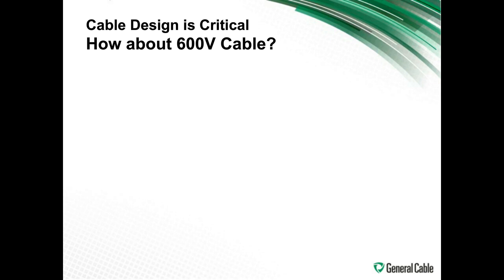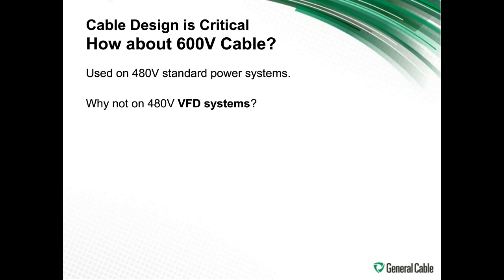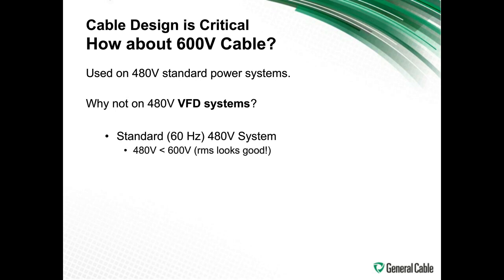So how about 600 volt cable? Let's look again at a 480 volt standard power system. Can we use it on a 480 volt VFD system? It's fine on the 480 volt standard system because the RMS voltage on a standard system is 480 volts. And the peak voltage from a standard system is 678 volts. But it's rated to 850 peak voltage for that system.